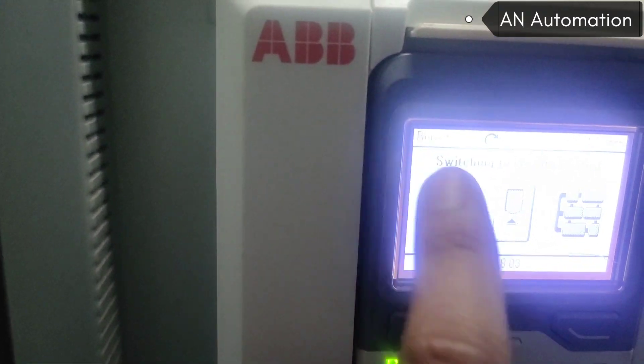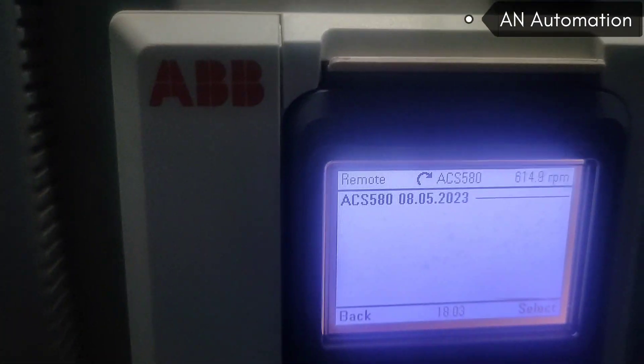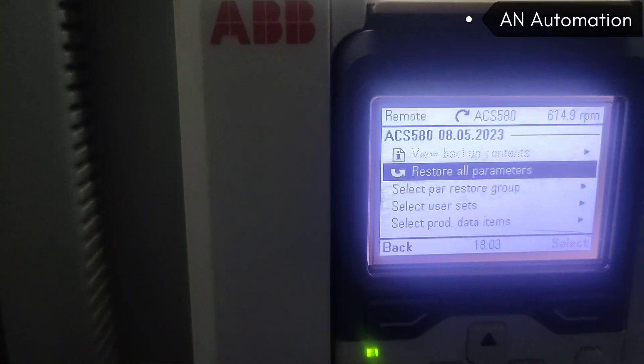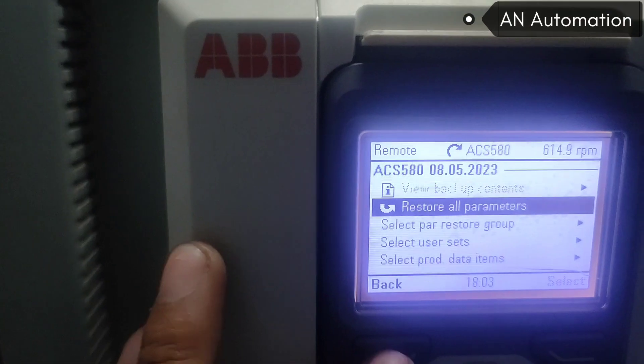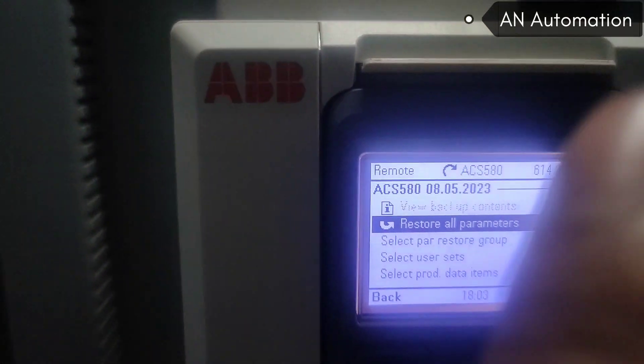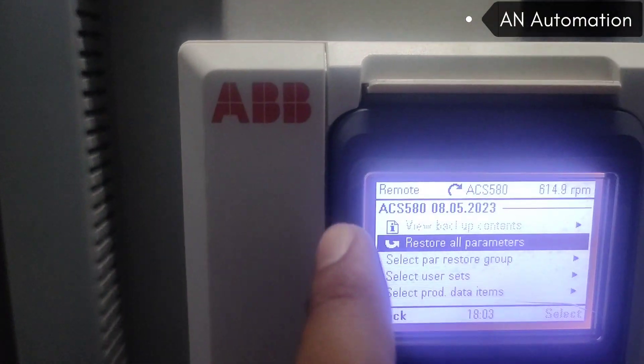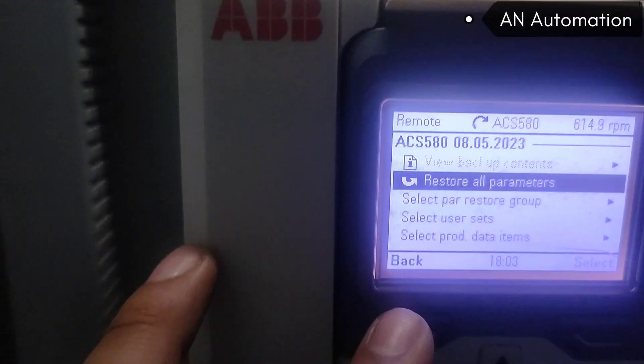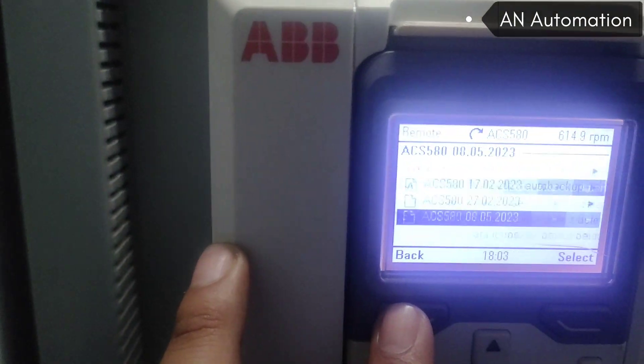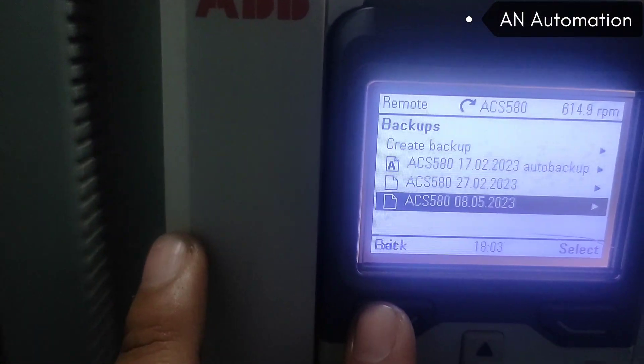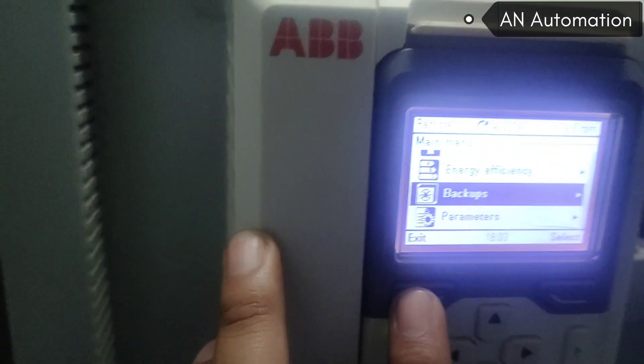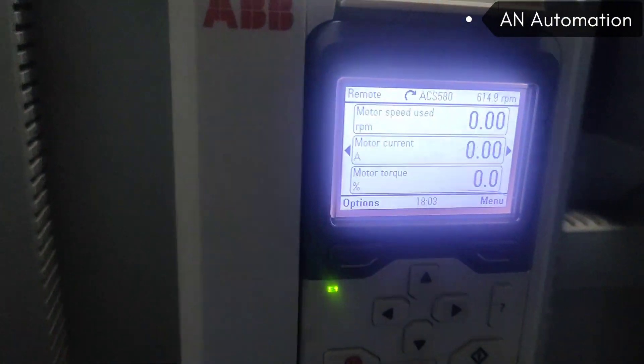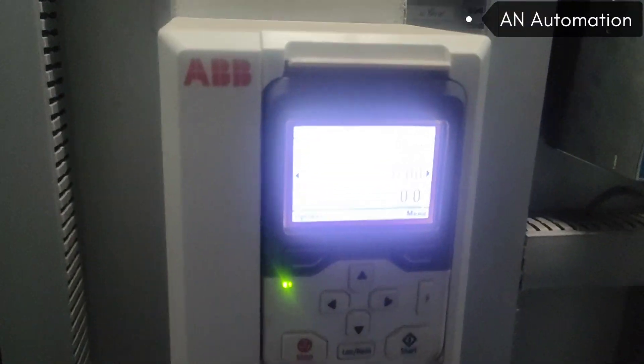Here you can see the remote option. When it is in remote, you cannot restore all parameters. So after selecting local, you will have to select 'Restore All Parameters' and click to confirm. Then parameters will automatically be downloaded from the BOP to the drive.